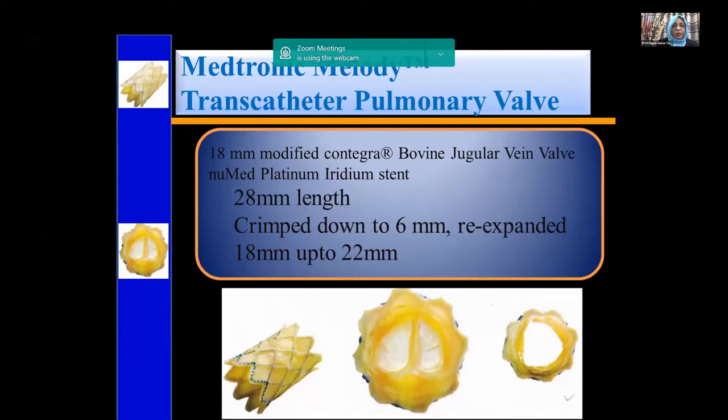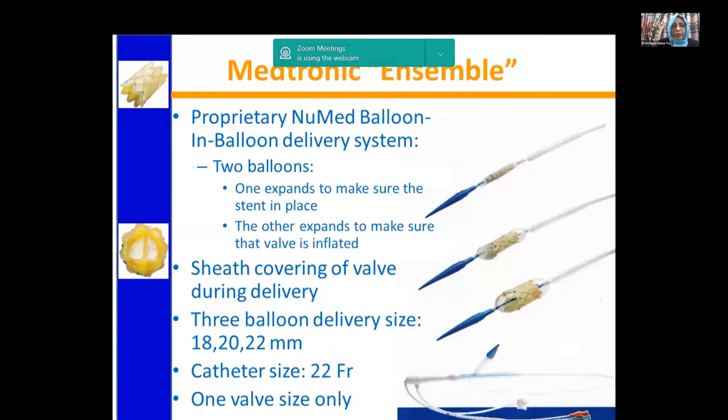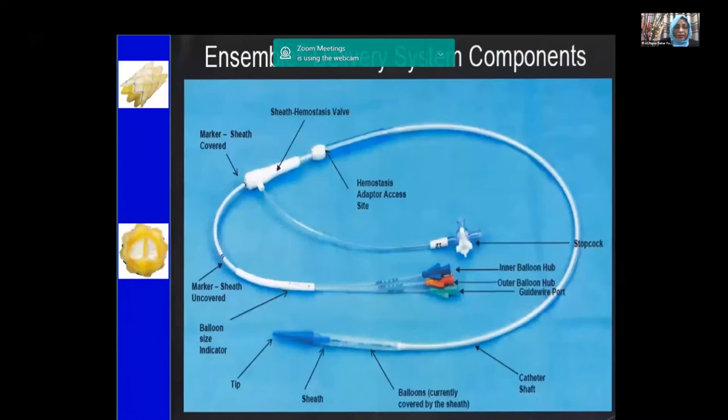The Medtronic Melody transcatheter pulmonary valve is actually a Contegra type of valve made from a bovine jugular vein with a length of about 28 mm. It can be crimped down to 6 mm and then re-expanded into three sizes — 18, 20, and 22 mm — using the Ensemble delivery system. The Ensemble delivery system has three ports: one for the inner balloon, one for the outer balloon, and one for the wire. This valve is inflated with the BIB (balloon-in-balloon) balloon.